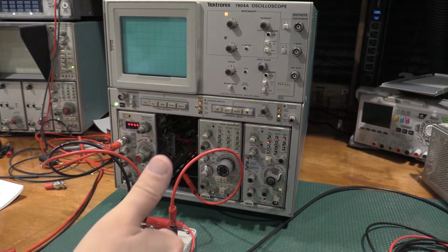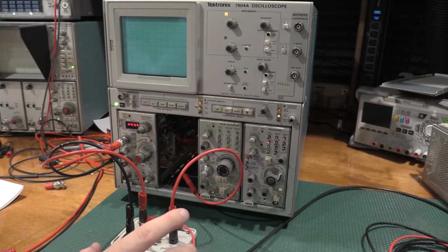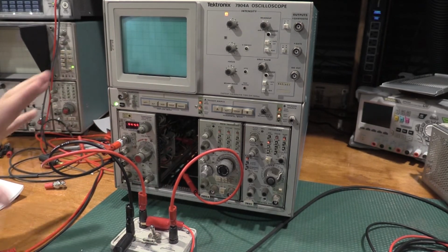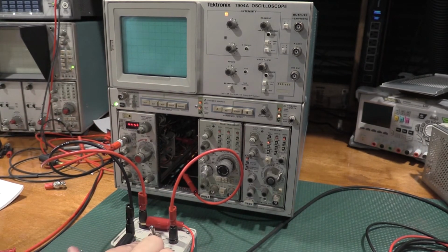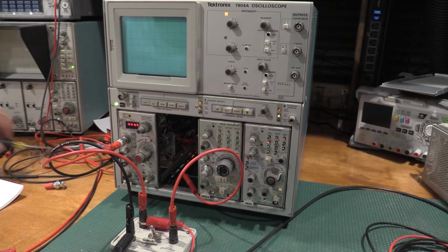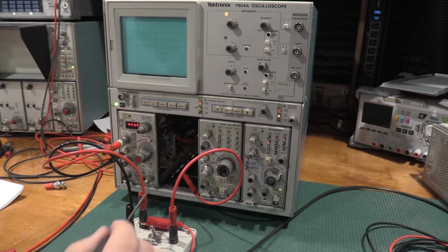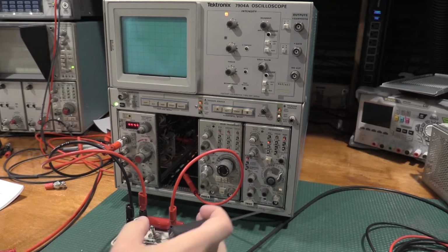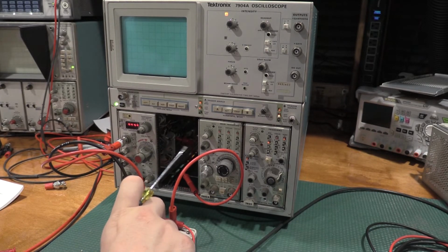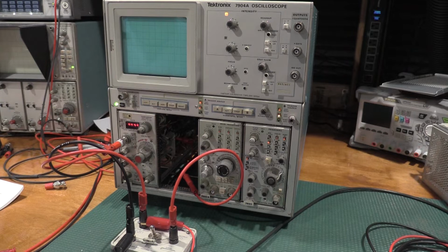Okay, we have the precision DC resistance standard set up as before. Exactly the same way. The 1 megohm resistor is back here. I'm going to get a couple of these 1 megohm precision resistors. I'd like to not have to move this one off of here again. Also, we've moved this switch into the 100X position. It was at the 10-to-1 divider. Now it's a 100-to-1 divider. We're going to fire this up again. I need to turn the voltage standard back on. Haven't adjusted that, so it's still at 50 volts, which is fine. And operate.